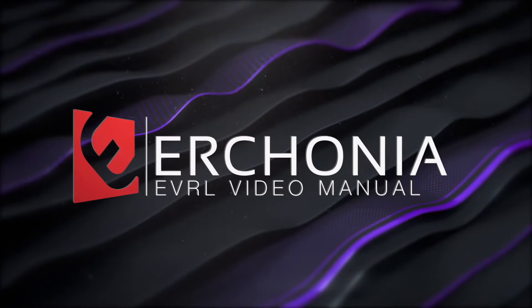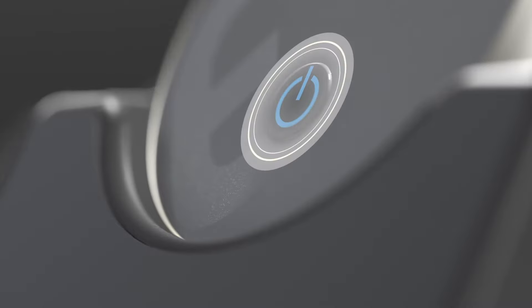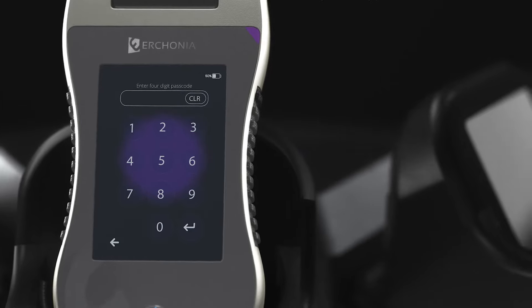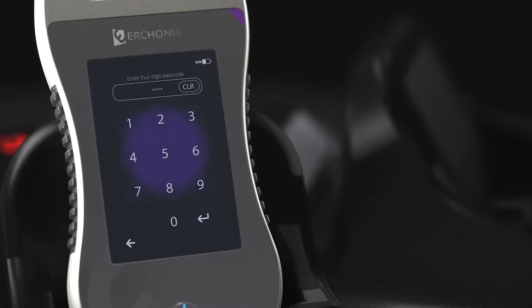Now let's get started. We're going to go into the programming of the Erchonia device, which will have a digital portion to show you exactly how it's programmed. To power on, hold the button for three seconds. The device will take about 30 seconds to initialize. At first startup, enter the default passcode 1234.